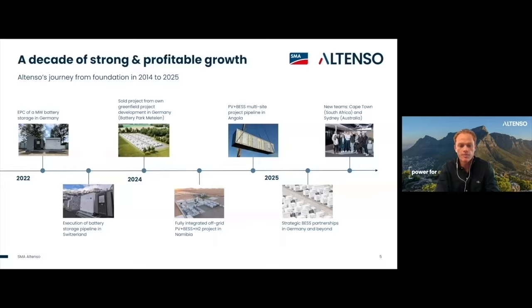And that was done in Walvis Bay in Namibia, in which we came on board as a system integration partner and integrated 5 megawatts of PV, 5 megawatt hours of BESS, and a 5 megawatt electrolyzer for the pilot phase of that project. And the objective and the rollout plan for that project is for it to reach a gigawatt. And there's essentially an anchor developer there, which is a Dutch shipping company. And they want to use the green hydrogen, or rather the green ammonia, to fuel their shipping fleet.